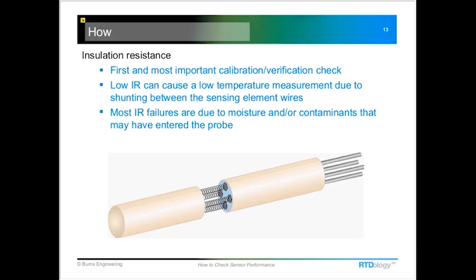One of the most important checks that we can do on an RTD is insulation resistance, and it should be the very first one that you do before you do anything else to it. What we're doing here is measuring how well the ceramic insulators here, and also where the lead wire connections are made back in this area, are working, just to make sure that there's no moisture or contaminants that are causing shunting between either the lead wires or between these coils of platinum wire inside the sensing element.